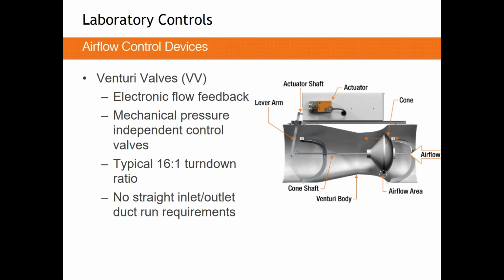That airflow is mapped for the whole device from minimum to maximum. Every single Venturi valve needs to be tested to understand what that position versus airflow curve actually looks like. So really what we're looking at are two separate mechanical systems in a Venturi valve. The lever arm and actuator shaft control your airflow volume, and the spring and cone assembly, you can see the cone being pointed to there, are what meter your pressure. So your pressure and airflow are two separate mechanical systems.